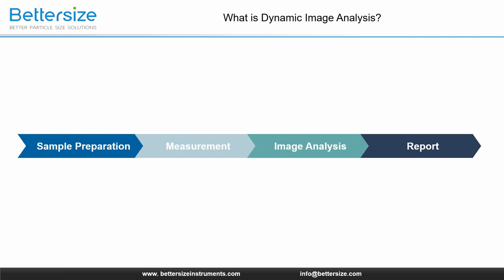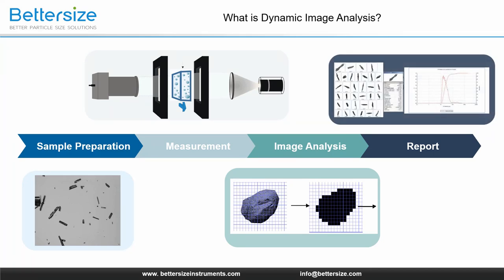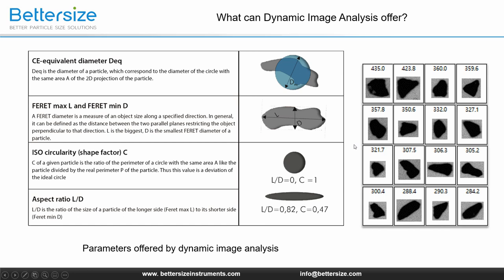However, laser diffraction does not provide information on particle shape or whether the calculated distribution corresponds to reality. So dynamic image analysis, another measurement method, can be used as a complementary system for particle size analysis. By counting the number of particles and the number of pixels contained in each particle projection, the equivalent circle area for each particle can be calculated. A complete dynamic image measurement includes sample preparation, measurement, image analysis, and report. It has the characteristics of being intuitive, visual, accurate, and having a wide measurement range. With dynamic image analysis, particle parameters including the equivalent area diameter, Feret max and min, circularity, and aspect ratio can be provided. It is a new particle sizing tool for research and production of powder materials.